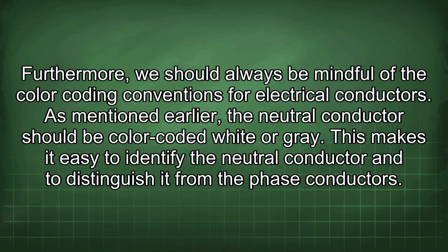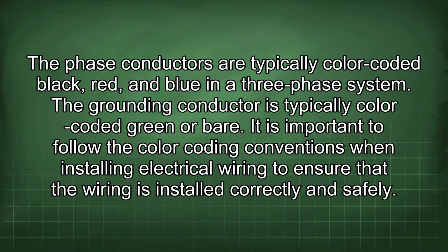As mentioned earlier, the neutral conductor should be color-coded white or gray. This makes it easy to identify the neutral conductor and to distinguish it from the phase conductors. The phase conductors are typically color-coded black, red, and blue in a three-phase system. The grounding conductor is typically color-coded green or bare. It is important to follow the color coding conventions when installing electrical wiring to ensure that the wiring is installed correctly and safely.